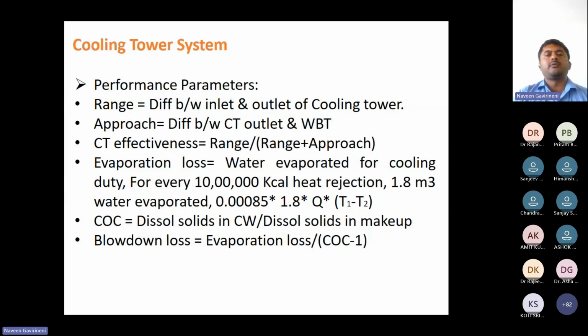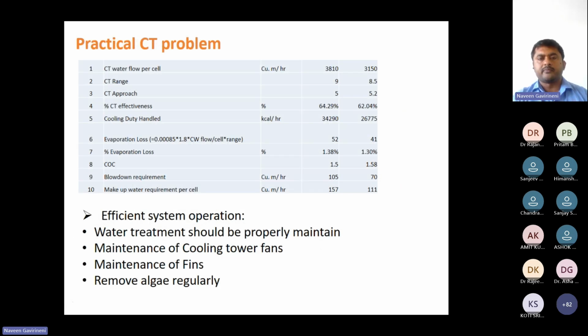How to evaluate the performance of the cooling water system? There are range, approach, CT effectiveness, evaporation loss, COC (cycle of concentration), and blowdown loss. Just go through that. These are practical problems. COC should be less than 2 only. If it is more than 2, you should concentrate on the water chemistry, and moreover on the algae formation in the cooling tower. You should be cautious.